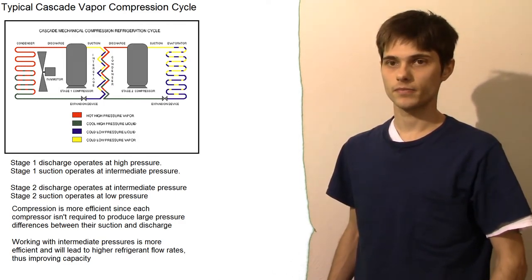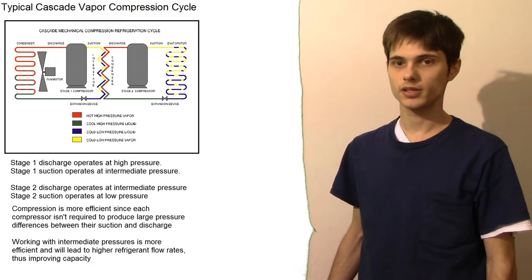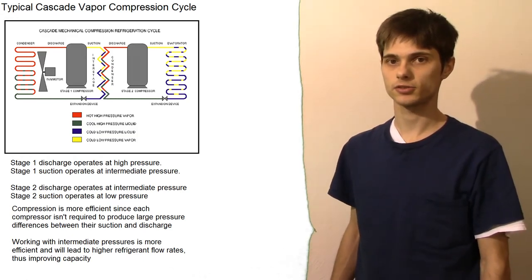Now, the intermediate pressure, or the suction side of the high temperature cycle, will be the evaporator and that will be the heat exchanger. Now, this part will be key to getting heat from the low temperature cycle up to the high temperature cycle.